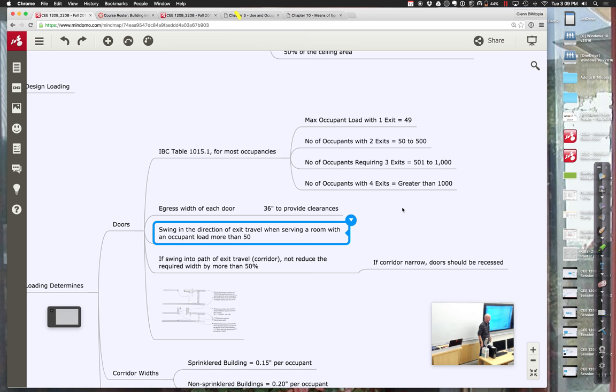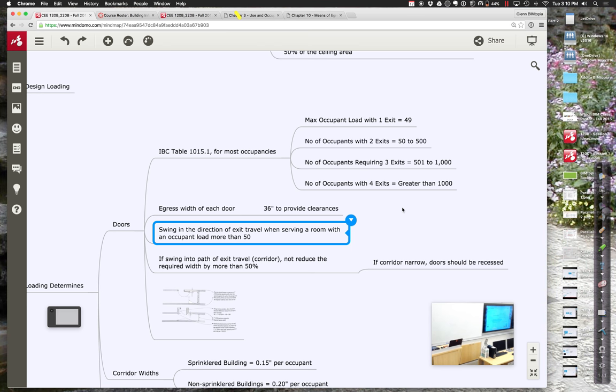If you have a room with up to 49 people, you only need one door. As soon as you cross 50 people, you need two doors. From 50 to 500 people, two doors suffice; an auditorium with 400 people could technically have just two doors. For up to 1,000 people, three exits are required. These are minimums — it's perfectly okay to exceed the standards and provide more doors.